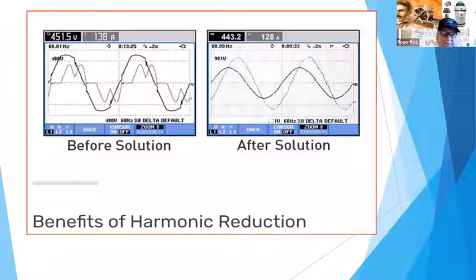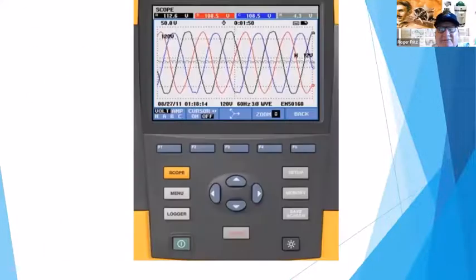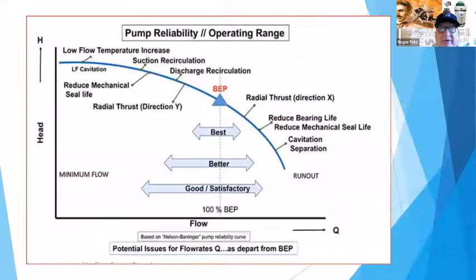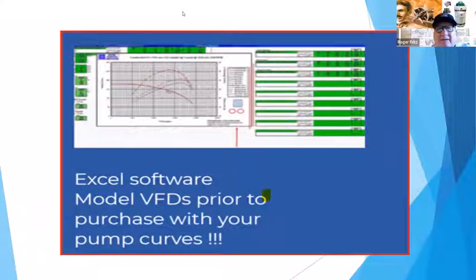They're going, oh yeah, well, I put the VFD on and I'm saving power, but they forgot to calculate the other factor. Back to where is that pump curve? Because what Rob showed me out of Australia blew my mind. The pump guys tend to give you one set of curves. They're designing it for an 1800 RPM machine or 1550 or whatever, and they're giving a curve: this is the best horsepower point, and this is the optimal point. So you should run in this tolerance range. But they could do a different bowl stack, and maybe instead of 3 sets of bowls, they go to 4 or 5. When you put the VFD on, maybe they should run together.